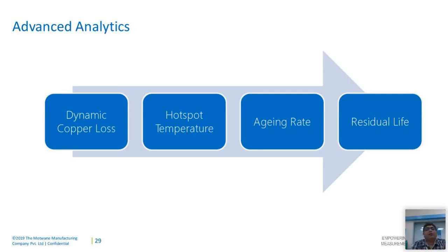Beyond that, this system gives you the dynamic copper loss. These are a very beautiful combination of the periodic data we capture and the live parameters. This particular functionality tells you the dynamic copper loss happening within the transformer. Since we are monitoring the load conditions in real time, we have the updated values of resistance. We monitor the tap positions in a live situation.